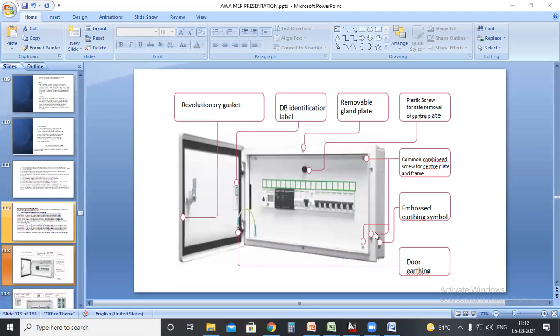If it is running a single phase motor, you can see this particular distribution board. But normally it will not be visible; this kind of DB is not available in other parts like GCC countries or British standard following countries. So this is the single phase DB. We usually select this when the load is lesser than 5000 watts. If the load is greater than 5000 watts, you need to select the TPN.